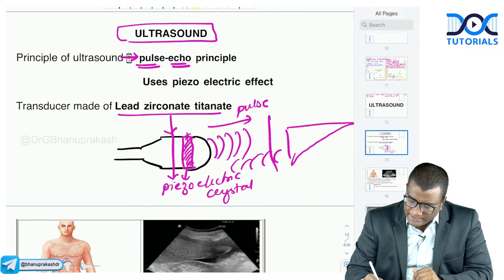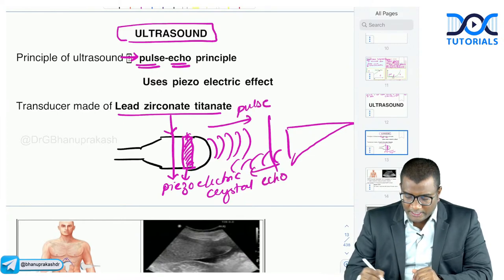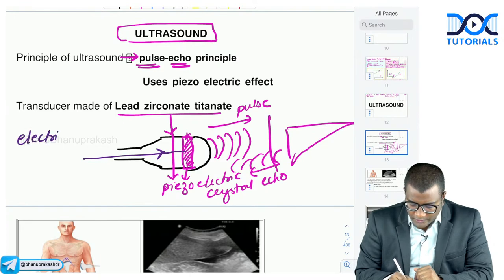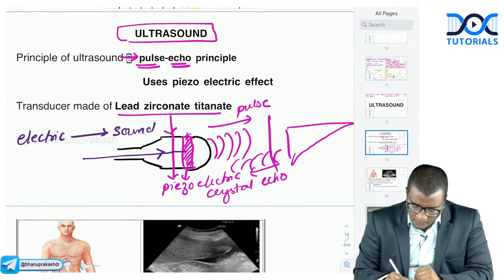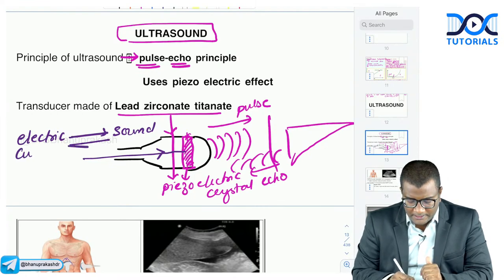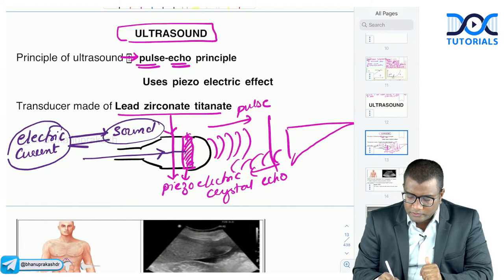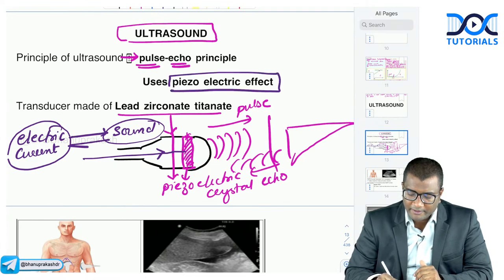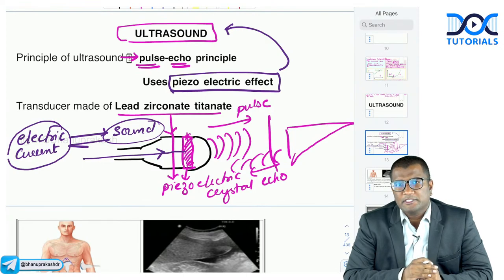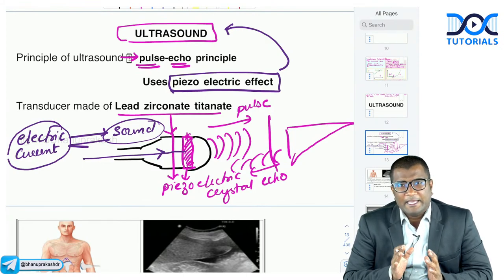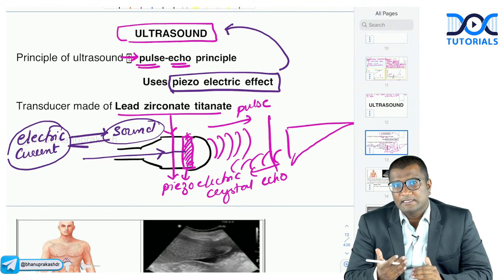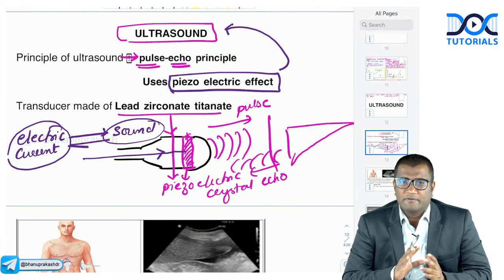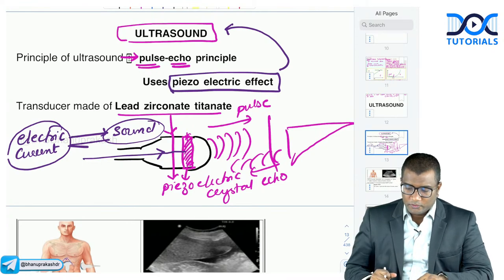The piezoelectric crystal converts electrical current into sound waves and converts the reflected sound waves back into electrical current. This property is called the piezoelectric effect. Ultrasound uses the pulse-echo principle and the piezoelectric effect. The transducer crystal — made of lead zirconate titanate — is responsible for this conversion in both directions.